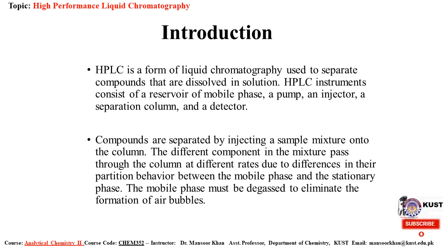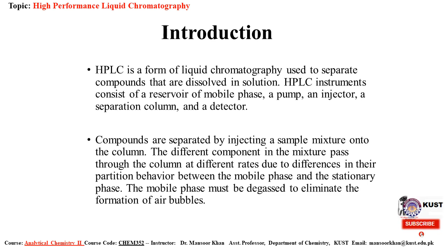The component of the sample which is to be separated is injected into the mobile phase, onto the stationary phase, where the eluent or mobile phase comes with high pressure and passes through the stationary phase. The components are partitioned between the two phases and separated, which depends totally on their solubility in the mobile and stationary phases. The mobile phase must be degassed to eliminate the formation of air bubbles.